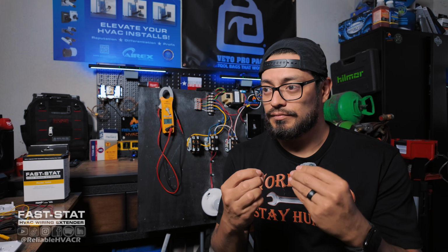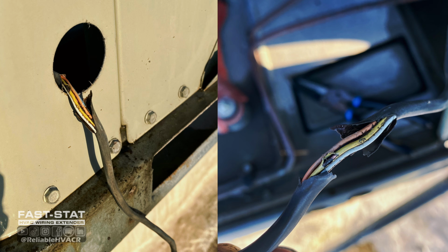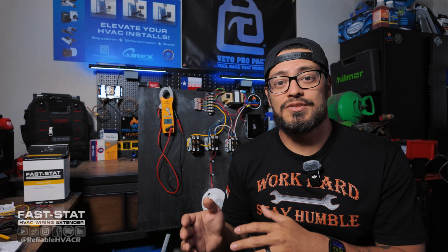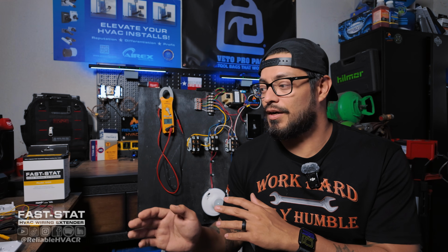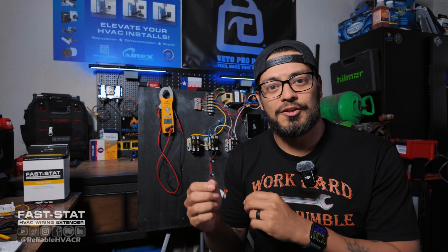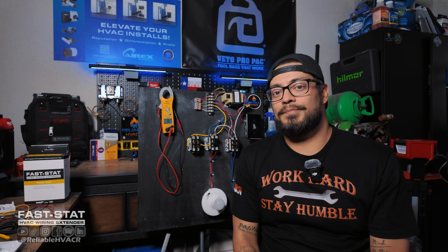So I've seen it with exposed thermostat wiring. It gets brittle. Either the jacket and sleeves start to deteriorate and we get shorts like that, or the wires themselves just get brittle and break. But you guys might deal with new construction where somebody cuts that thermostat wire, or the remodel renovation scenario, where they run a staple or nail through the thermostat wiring and cause a short or break that way. So just be mindful. Hopefully this was helpful in some way.